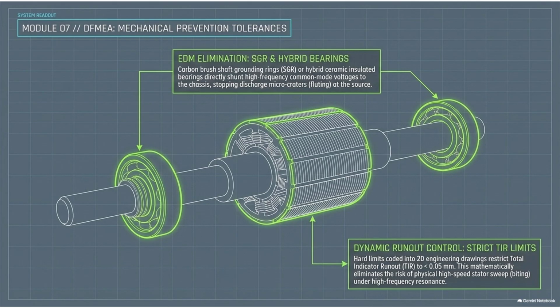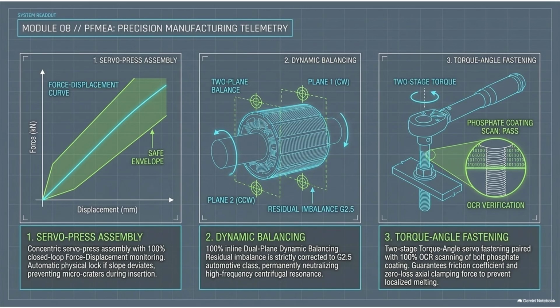Exactly. So they use a highly advanced two-stage torque angle servo tool. First, it tightens the bolt to a very specific torque setting. Then it relies on an angle measurement, turning the bolt an exact number of degrees further. This guarantees that the bolt actually stretches slightly, which acts like a strong spring permanently clamping the metal terminals together. But that isn't the amazing part. No, the amazing part is what happens before the robotic screwdriver even touches the bolt. The text says it uses OCR, optical character recognition cameras.